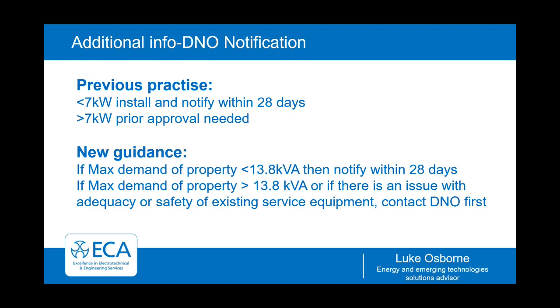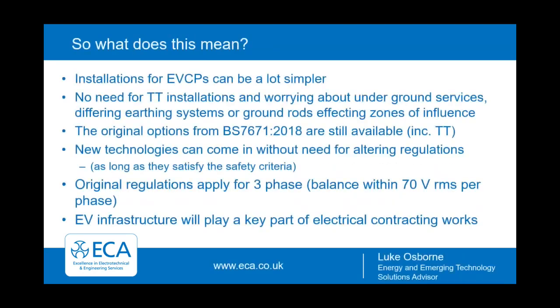To be honest, in many instances, the 7 kilowatt rule will still apply, but when heat pumps or other high rated equipment is in the installation, do be careful with the 13.8 kVA rule. So what does this all mean? Well, going forward, electric vehicle charge point installations can be a lot simpler. There is no specific need for TT installations or worrying about underground services or the differing earthing systems and ground rods affecting zones of influence, because the new regulation now permits this device that monitors the plus or minus 10%.